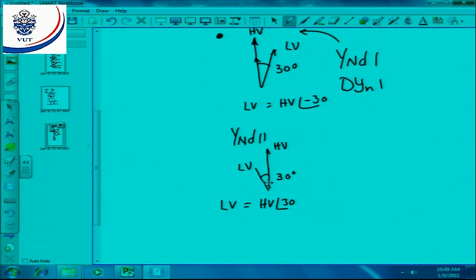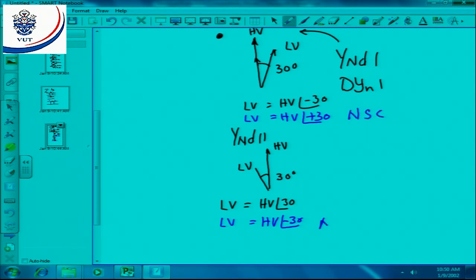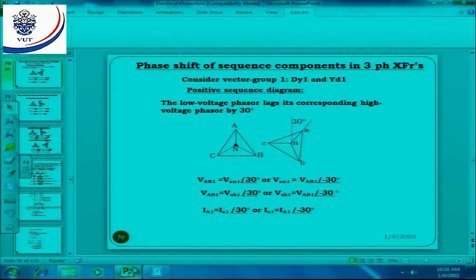Remember for negative sequence it is just the opposite. Here the low voltage negative sequence component is just the reverse. It depends on your transformer connection group — it's always 30 degrees or minus 30 degrees, either the 1 o'clock or 11 o'clock connection.